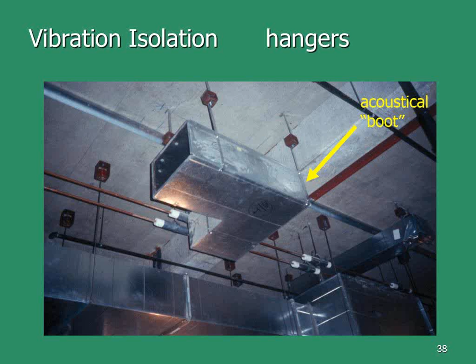Bob, why would you recommend, if we've got a piece of equipment connected to the ductwork, say, a fabric flex connector between the ductwork and equipment, does that not work to take out some of the rumbling? You recommend on some, say, a much larger air handling unit, you actually put your ductwork on spring isolation hangers? The question for the web is, do we go just beyond the fabric flex connector at the air handler? Isn't that good enough?